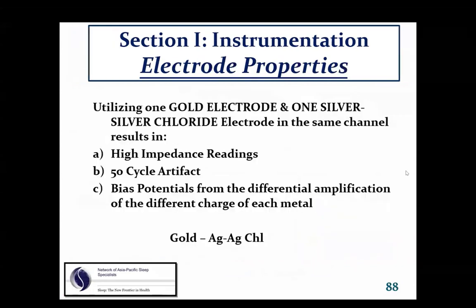When we talk about electrodes, if we have multiple metal types in our lab, using one, for instance, gold and one silver chloride electrode in the same channel results in not high impedance recordings, not 50 cycle artifact, but rather activity that looks like real physiologic activity, representing the difference between the metal value. So these are called bias potentials from the differential amplification of the different charge of each metal. So we would never want to have a gold and a silver chloride electrode.